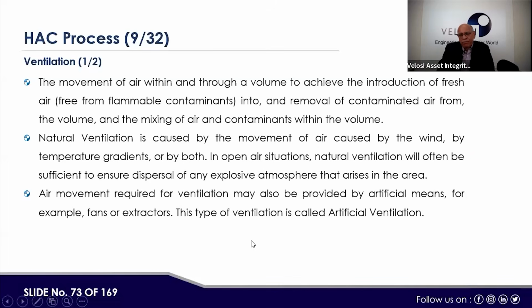So ventilation: what is the purpose of ventilation? If hydrocarbons are released from any equipment or piping system, valve or vent, they should not remain present in that area. If they accumulate, it could be a cause of explosion anytime. So for certain areas, we do apply ventilation. In open plant areas, plants are designed in a way that sufficient space is available where air may provide ventilation, and hydrocarbons are not contained in that area. Hydrocarbons released from equipment are of two types: gases lighter than air, which will go above, and gases heavier than air, like H2S, which will go along the ground surface. So for both reasons, we need to keep a ventilation system.